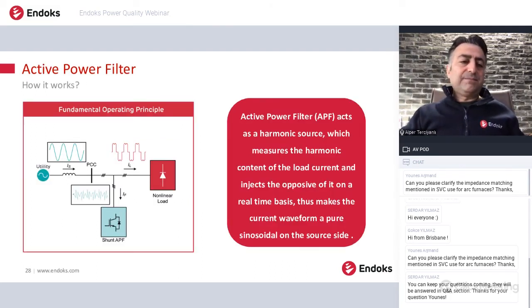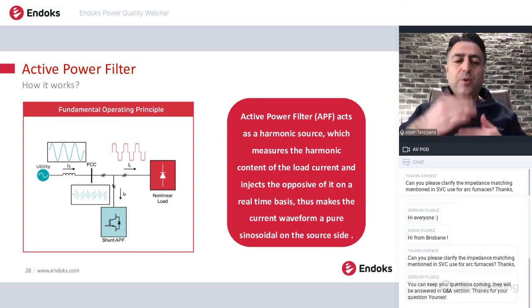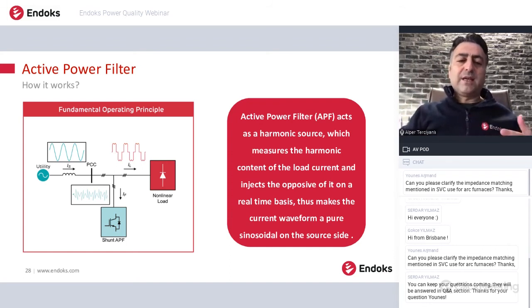And active filters are almost the same as STATCOMs. We have the same converter topology, but here the active filter is controlled in a way that generates harmonic currents. So how it works: we have a nonlinear load. It creates a harmonic waveform with fundamental and harmonic currents. So we measure the harmonics, and we inject the opposite of these harmonics. So we cancel the harmonics at the point of common coupling. So the current on the grid side becomes pure sinusoidal.